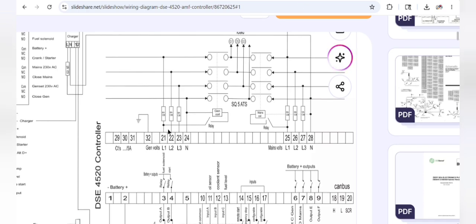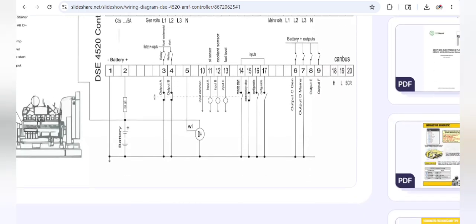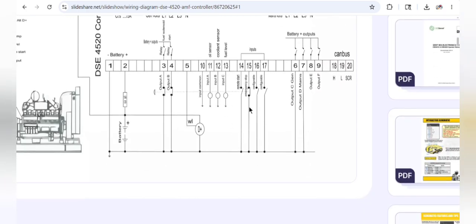When the main power is not available and the generator power is available, the generator contactor will be closed, and the generator load will be shifted onto the load. Understand? So let's move to the pin 14 remote start wiring circuit diagram.